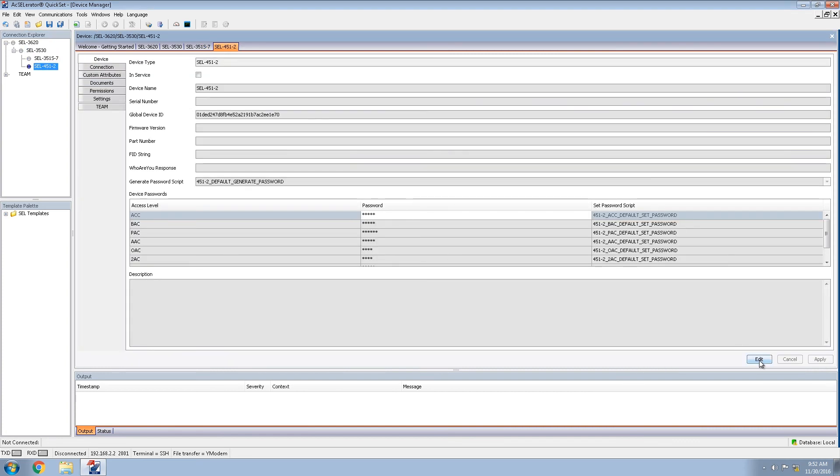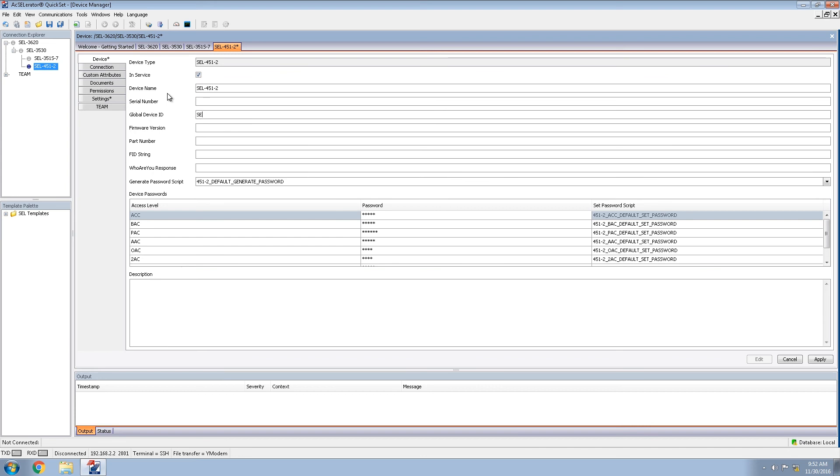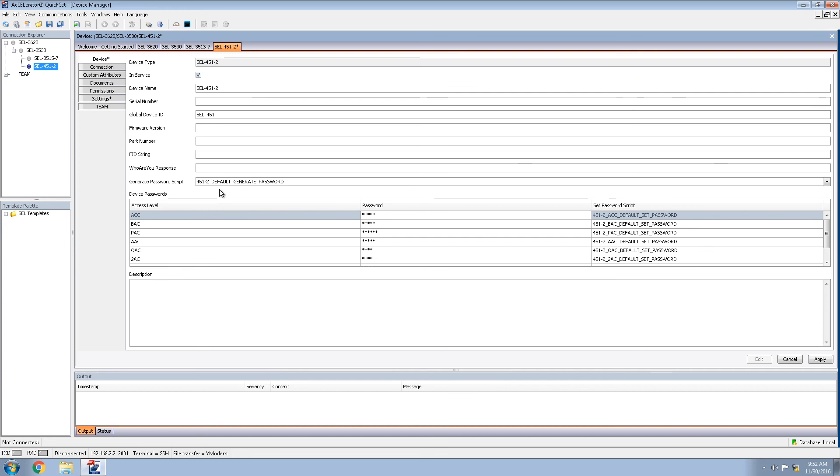For the 451, edit, in service, and provide a global device ID meaningful to us, SEL underscore 451 in this case. You will notice that this is a 451-2, which means that we do have the legacy password restrictions of six characters. The default generate password script for the 451-2 does incorporate that knowledge into the system. This allows us to spread six character passwords with a maximum variability in the character set used.